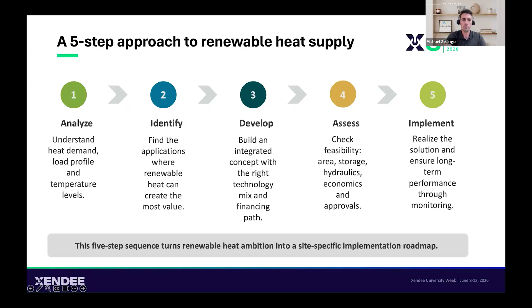So not every site is equally suitable for solar thermal or for decarbonizing the heat. So project selection matters. A good project usually starts with suitable roof or ground areas and good solar access. This is crucial when it comes to solar thermal integration. It also needs a matching load profile. Ideally, a stable heat sink with daytime demand, summer demand, or both.